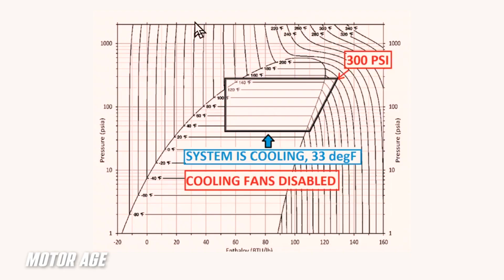Now, as you can see here, the temperature of the refrigerant entering the compressor is above freezing, about 33 degrees Fahrenheit, keeping us close to the bell curve, but still in the superheat zone, just as we desired. However, as we compress the refrigerant and pressure begins to build, since we can't shed heat across the condenser, our head pressure has reached over 300 pounds per square inch, pushing us further and further away from this bell curve. However, the condenser can still shed heat and bring us into the subcooling state we see here.